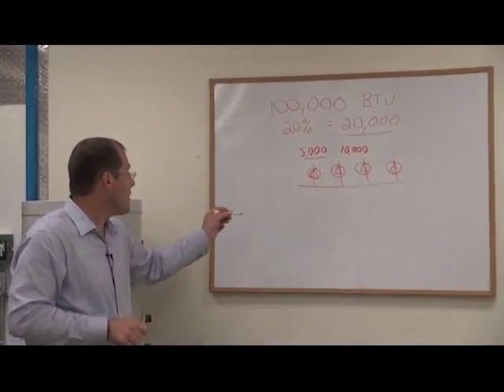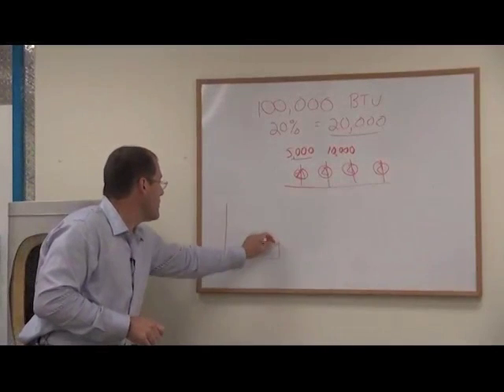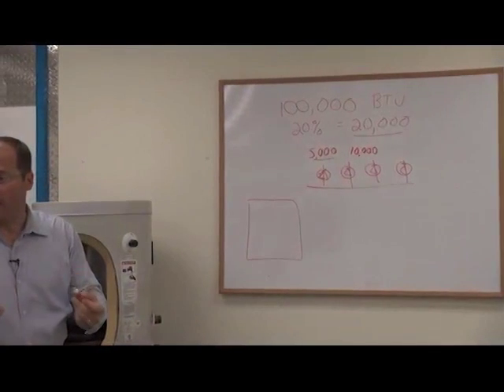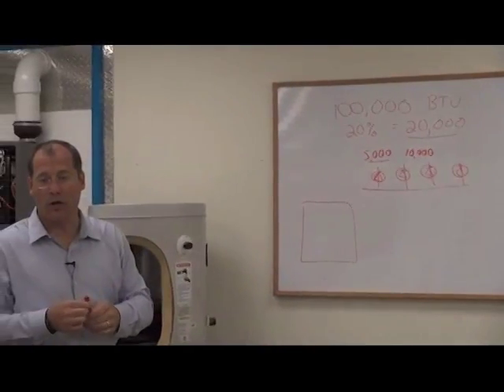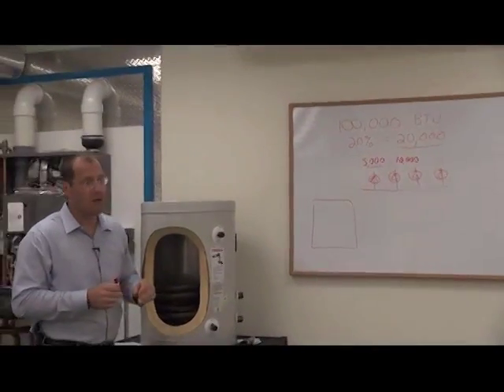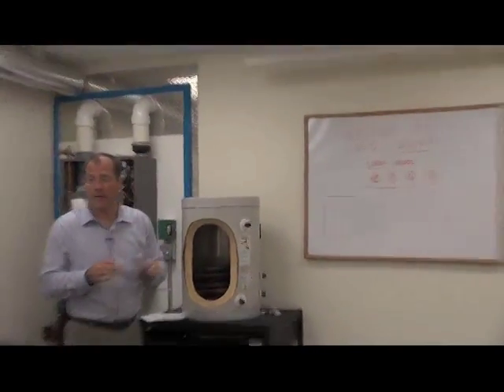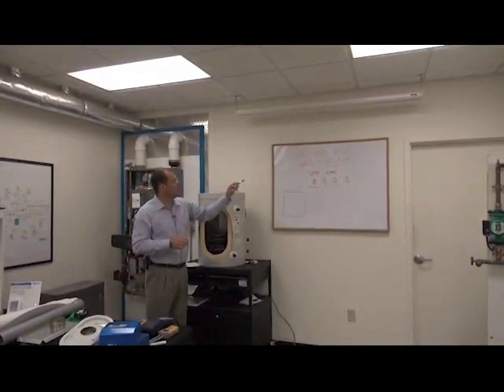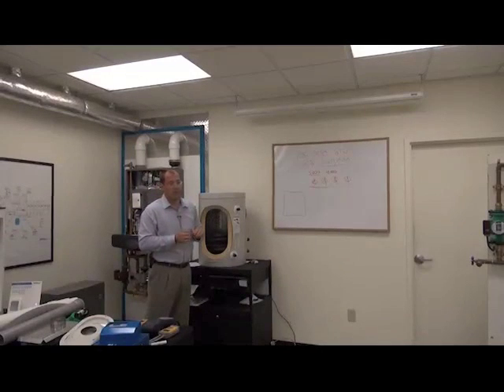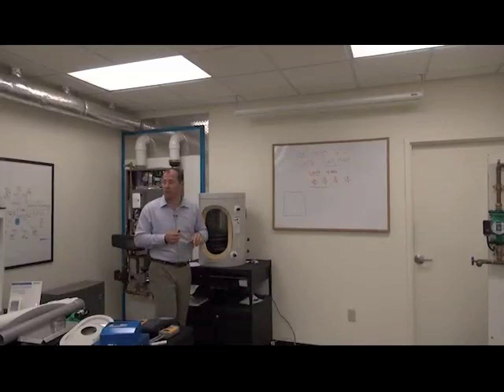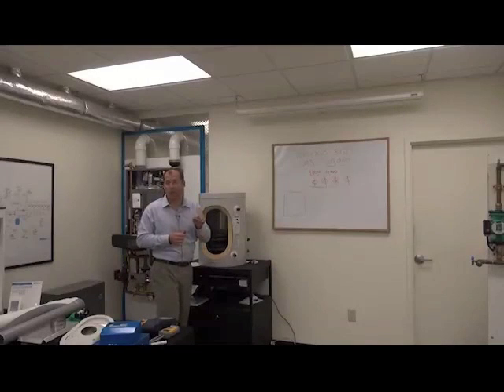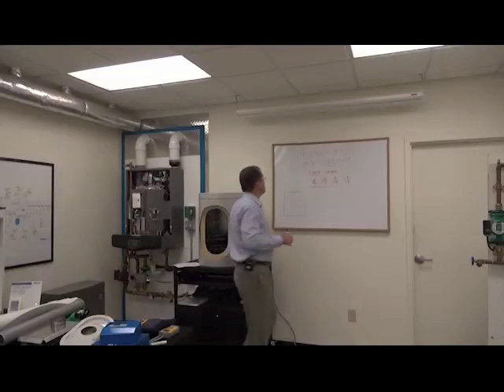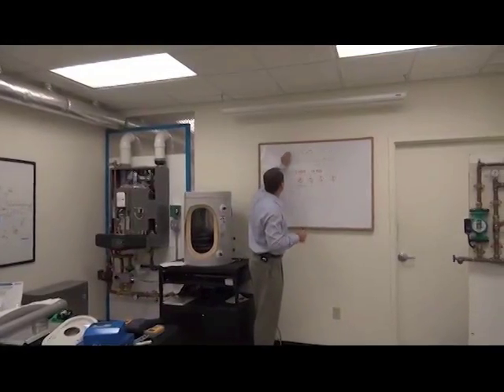The larger mass boilers that had all this water volume could satisfy that for quite a while before having to turn on. So your installing contractor has to be conscious of the size of the zones in order to try to minimize short cycling. There's some piping practices and things that we can do if there's lots of small zones to prevent short cycling. But the most important thing he can do is size this right.